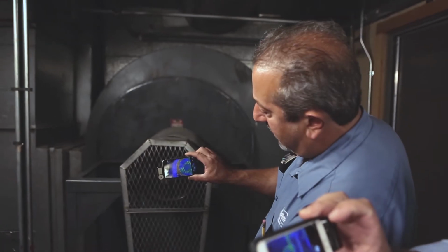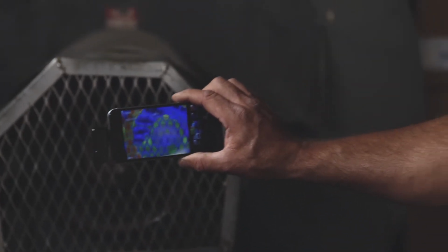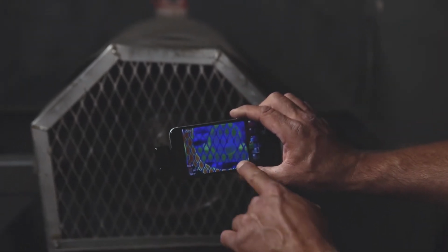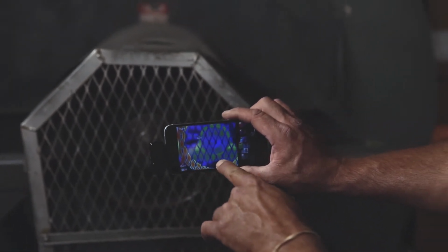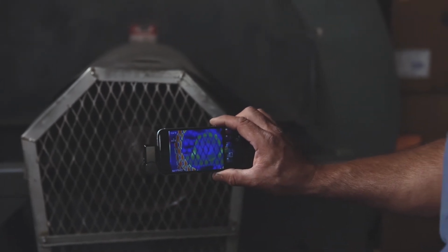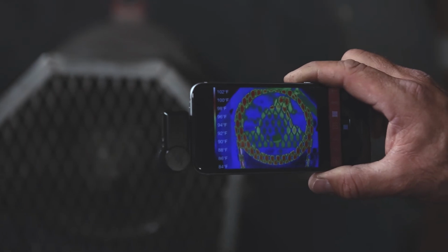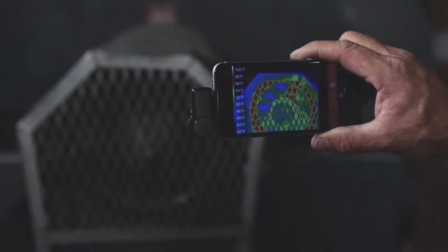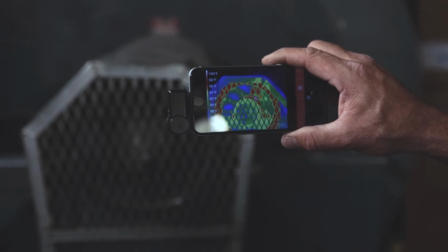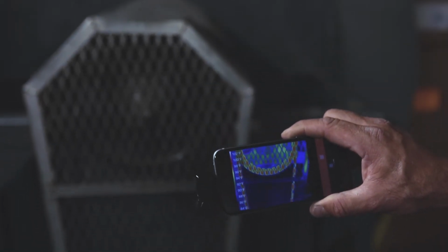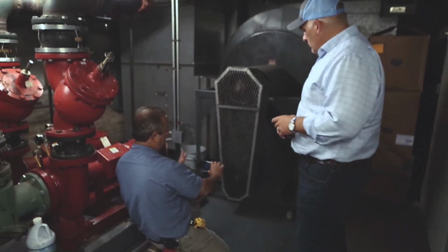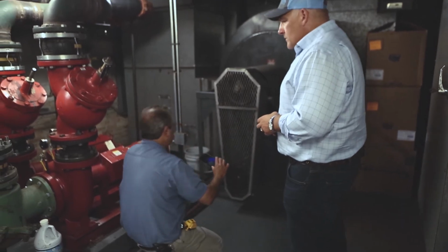Here's the pulley running, with a cage behind it. You can see the thermals all the way around, including the bearing. This is a running unit, and the bearing temperatures are pretty even and consistent, a good temp. That's our automatic span and level, compressing the entire color spectrum into the temperature range from 82 to 100. You get a lot of detail, you can even see the fans whirring around. There's the motor on the bottom running, reading 91 to 93 degrees at the bottom pulley, so it's pretty much an even keel.